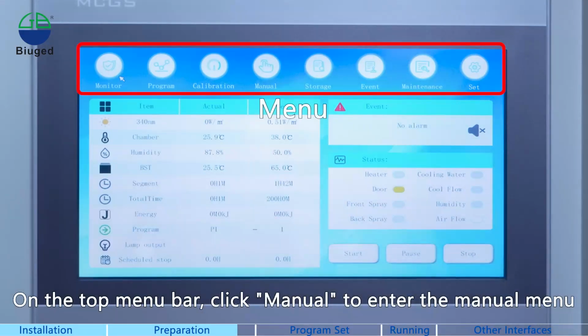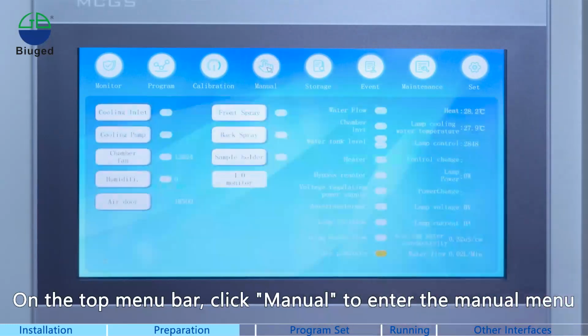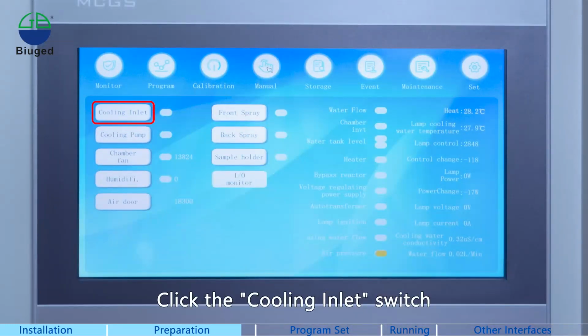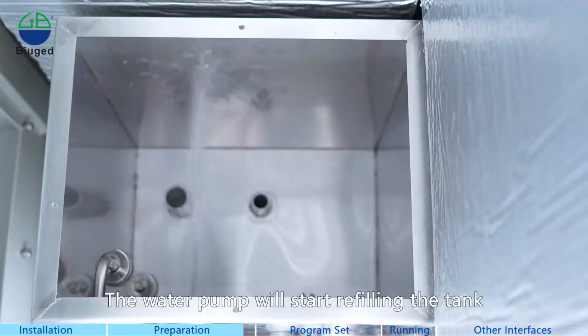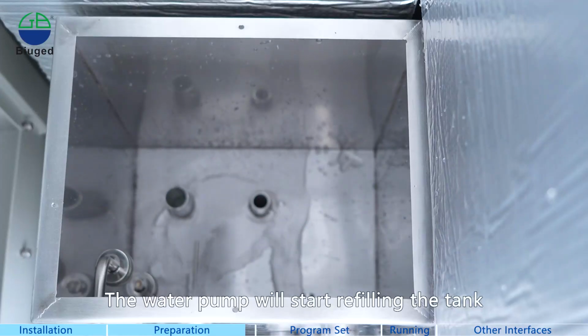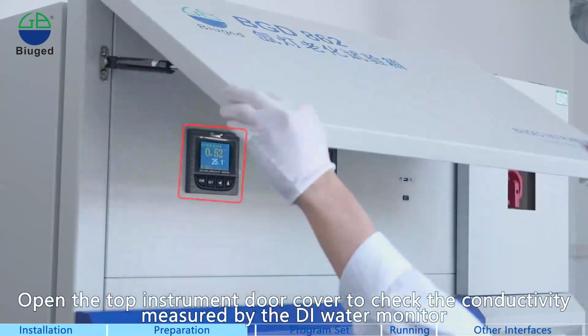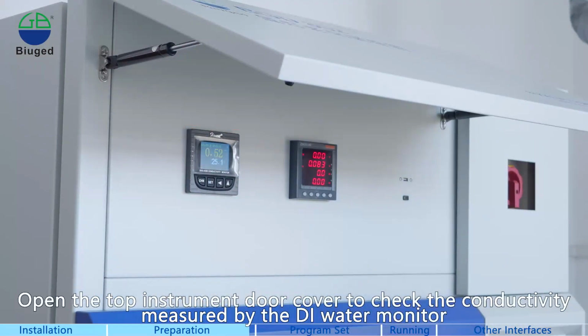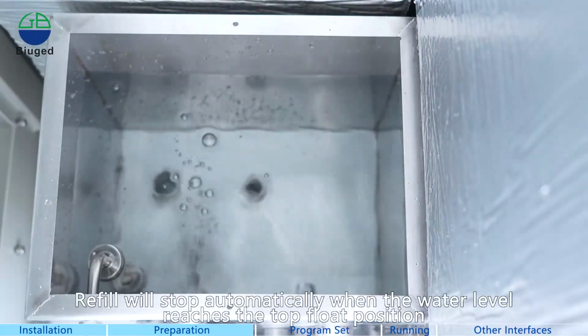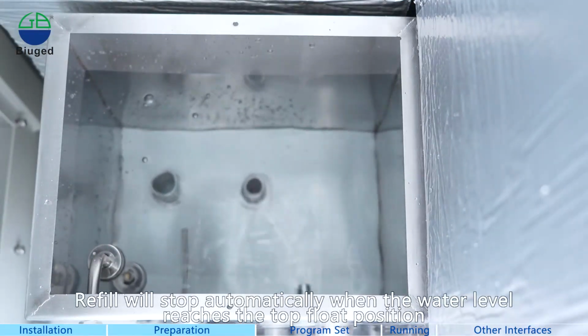On the top menu bar, click Manual to enter the manual menu. Click the tank refill switch. The water pump will start refilling the tank. Open the top instrument door cover to check the conductivity measured by the DI water monitor. Refill will stop automatically when the water level reaches the top float position.